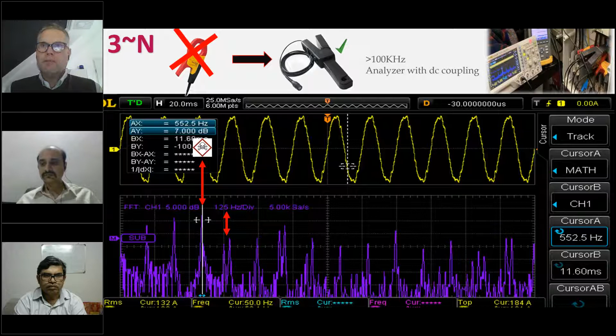But what was confusing was that it's going up and down, up and down. Because outside we have a lot of chargers and they are just standing there, nothing is happening, nobody is driving away. So it's not coming from the chargers area, it's coming from somewhere else. Let's investigate where this 11th harmonic and this 13th harmonic are coming from.